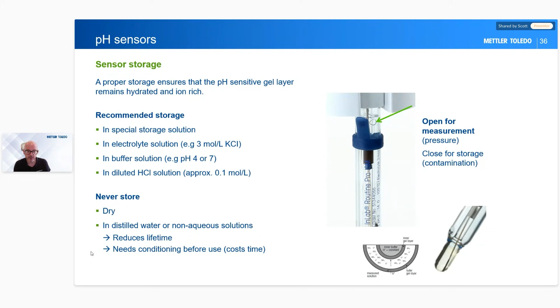So once we know how to store it, the next thing is the electrolyte inside the sensor itself. We said that when we're taking a reference reading, we want it to remain constant and steady, in which case we must have a constant electrolyte inside. Now these can be either gel-based or liquid-based. If it's gel-based electrolyte, then we don't need to do anything. The gel in there is stable, it's not going anywhere, and we're absolutely fine to leave it alone.